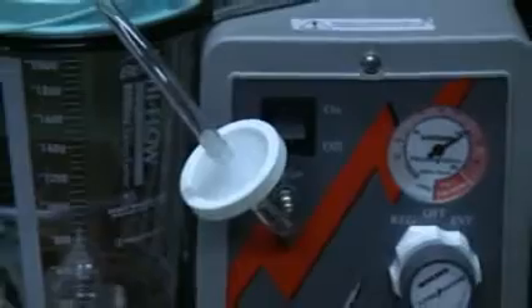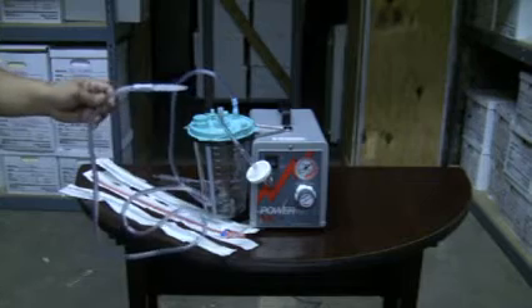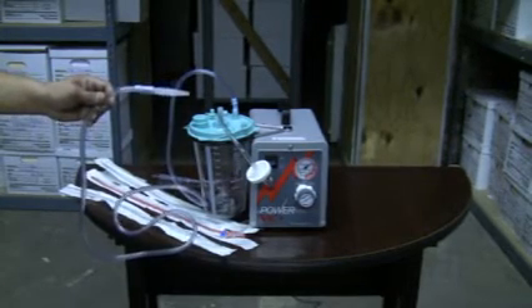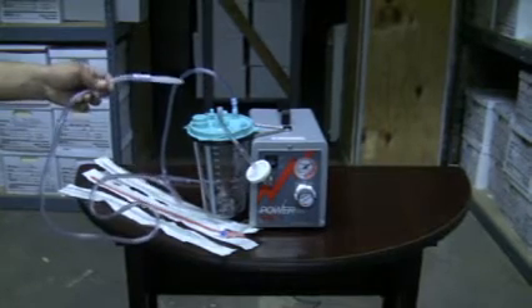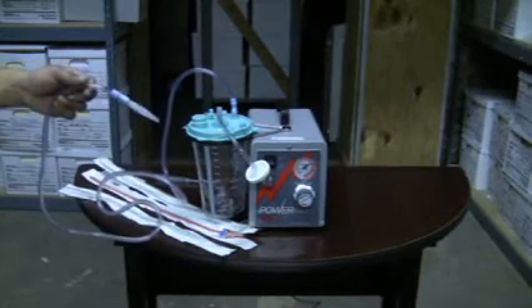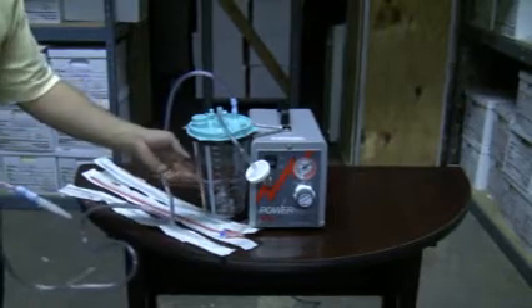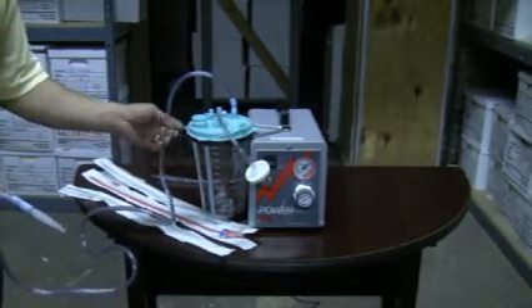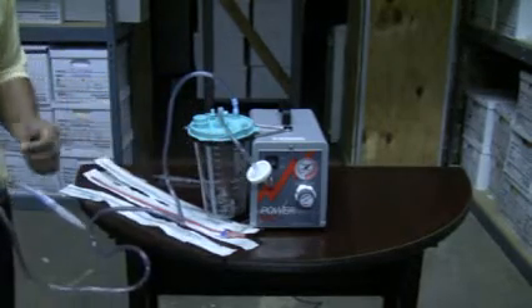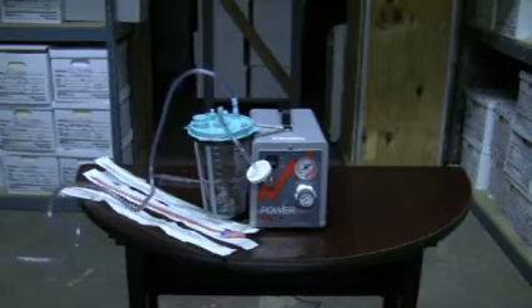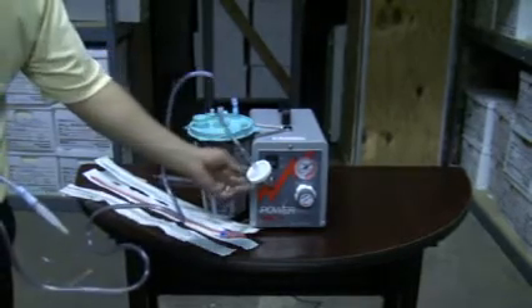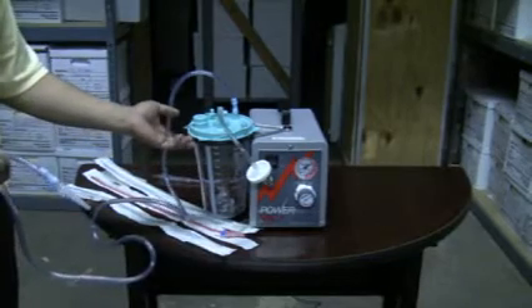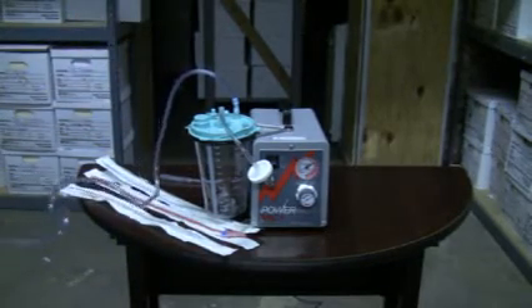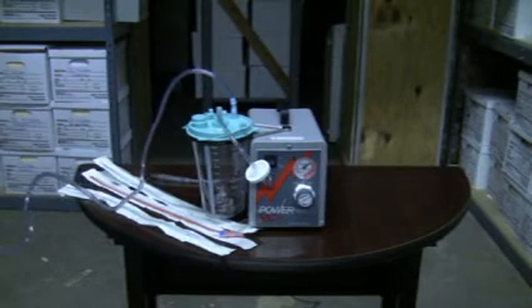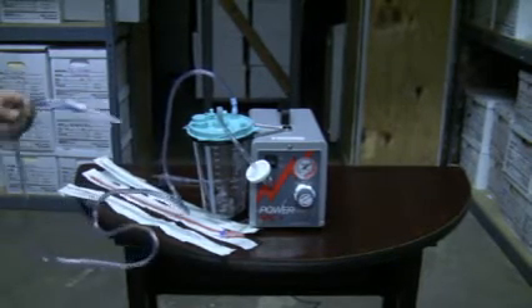If during the course of use you do experience your intermittent suction machine to stop where there is no vacuum pressure at the gauge or at the tubing, your canister may have become overfilled, or it has backed up into line into your overflow stop protection filter. If there is a backup into the line of your overflow stop protection filter, or your canister has become overfilled, that will also cause your intermittent suction machine not to provide your vacuum pressure in order to vacuum the patient properly.